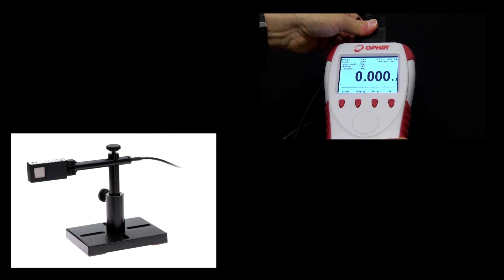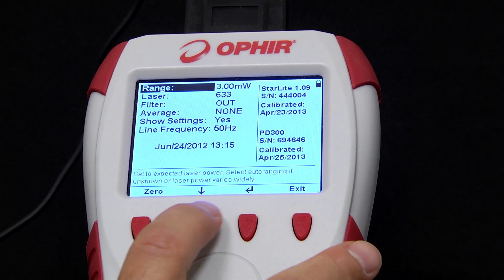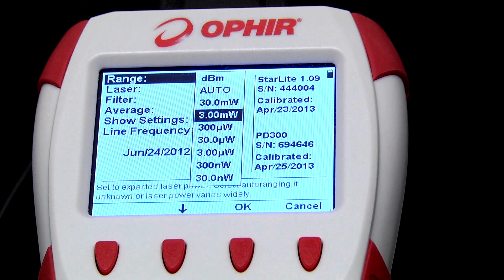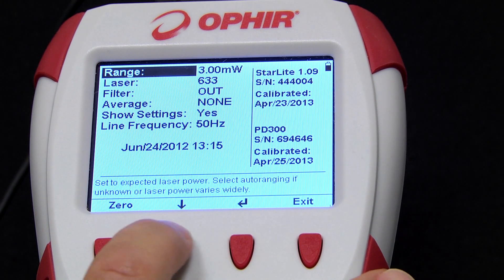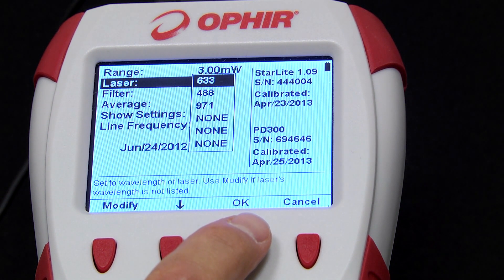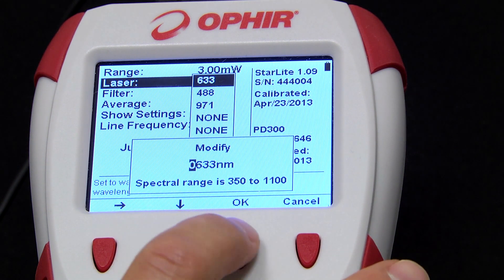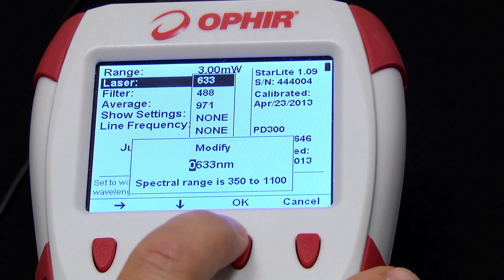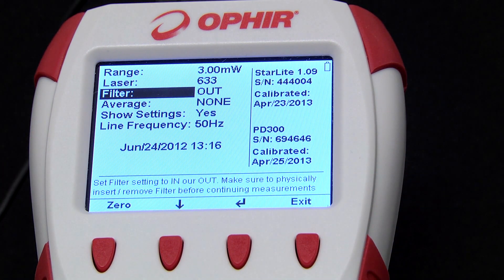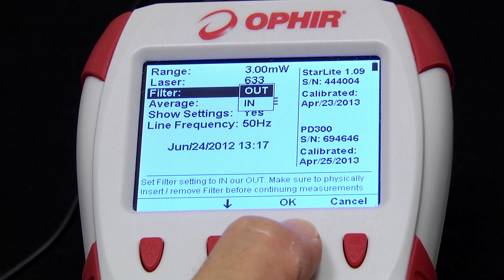We'll now switch to the PD300 photodiode-based power sensor for measuring very low powers, and again we'll focus only on those parameters that are different. The range includes the usual power scales plus dBm, which are units used in certain telecom and other fiber-related applications. For Laser, the user is prompted to select an explicit wavelength — a default set of favorite wavelengths is shown, and we can modify any one of those to the wavelength we need by going into the modify screen. Filter in/out: these sensors have an add-on filter which provides additional attenuation to enable the PD300 to work at higher power levels, and here is how we inform the StarLite that the filter is in or out.